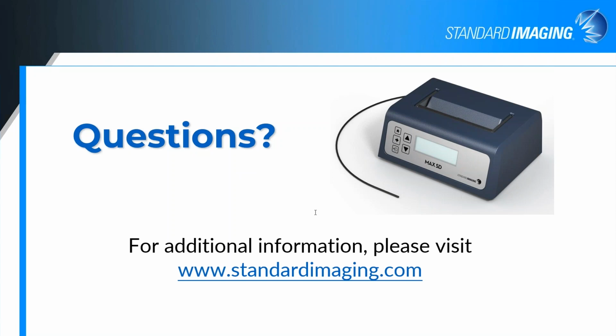How would you do a calibration? After you do your Cherenkov characterization measurements, so that minimum fiber configuration, maximum fiber configuration, the exact dose to the scintillator doesn't matter so much. You need a little bit of buildup because the Cherenkov effect also depends on having electronic equilibrium or changes depending on that. But after you've done those characterization measurements, you would want to do a measurement in a reference field. So for a standard linear accelerator, you would do it in your 10 by 10 field at your reference depth, give it a known dose. And our system is designed so you can put in, for these measurements, this is my known dose, and it will create that calibration factor that's then multiplied by subsequent measurements in order to convert to dose.